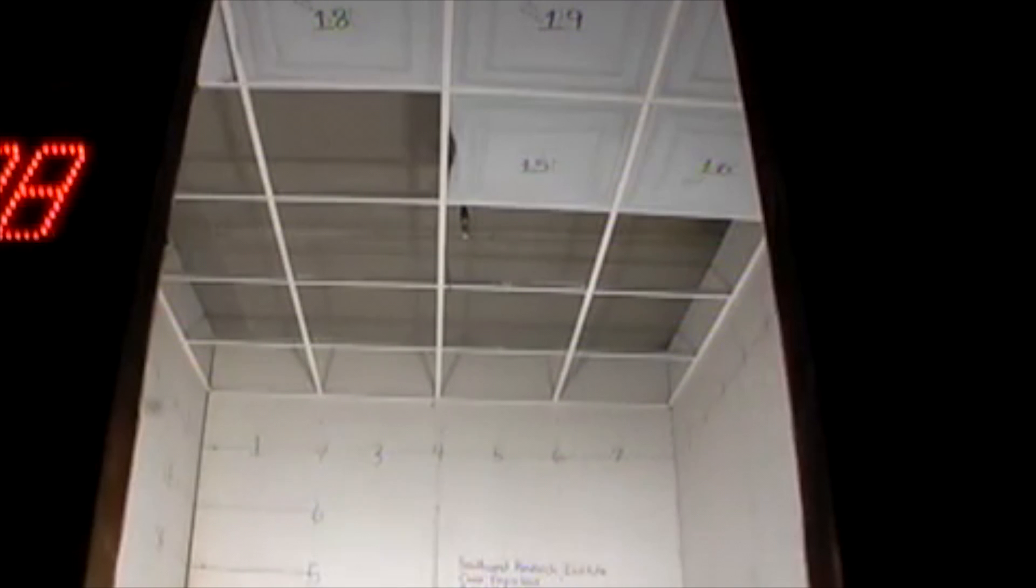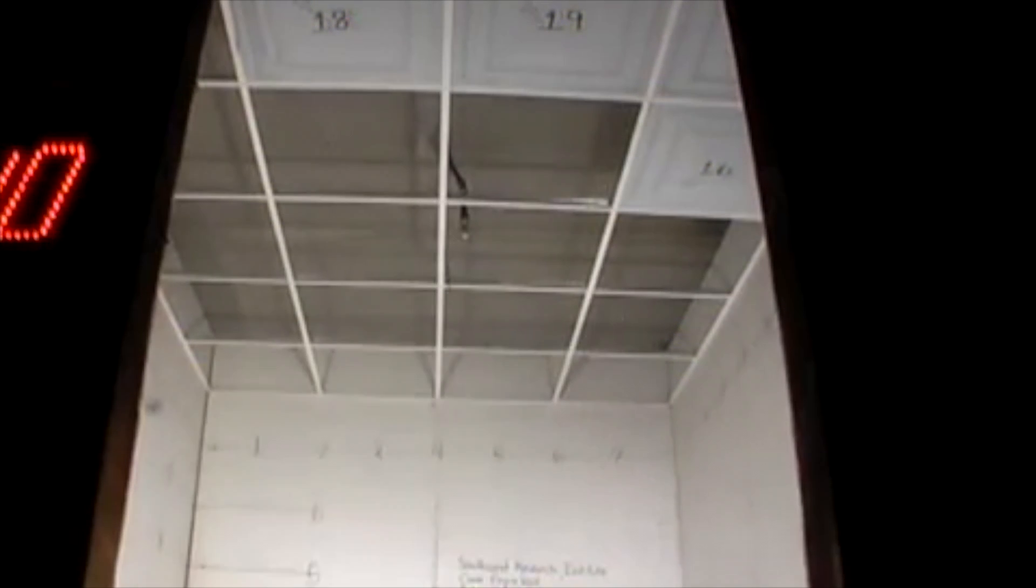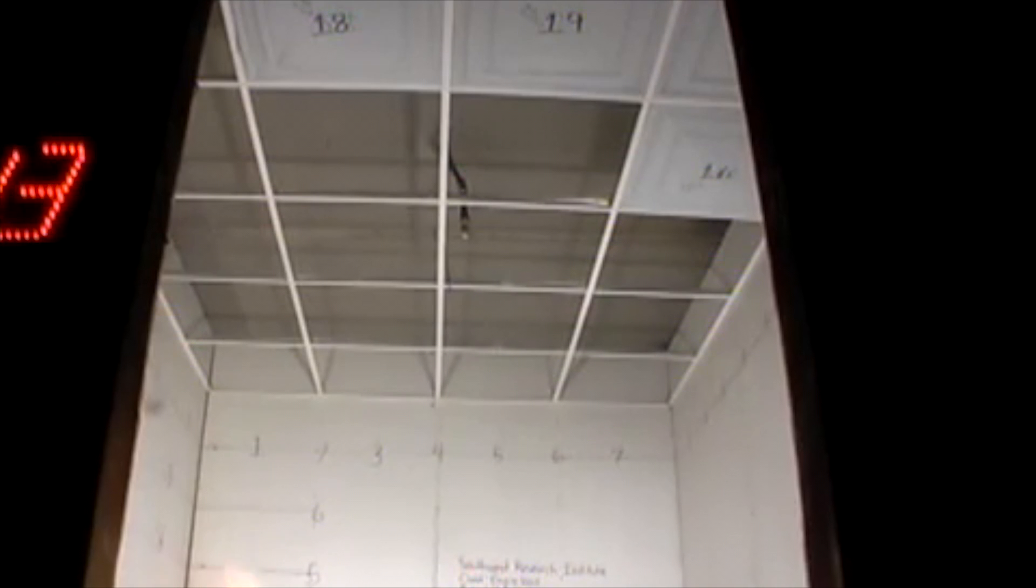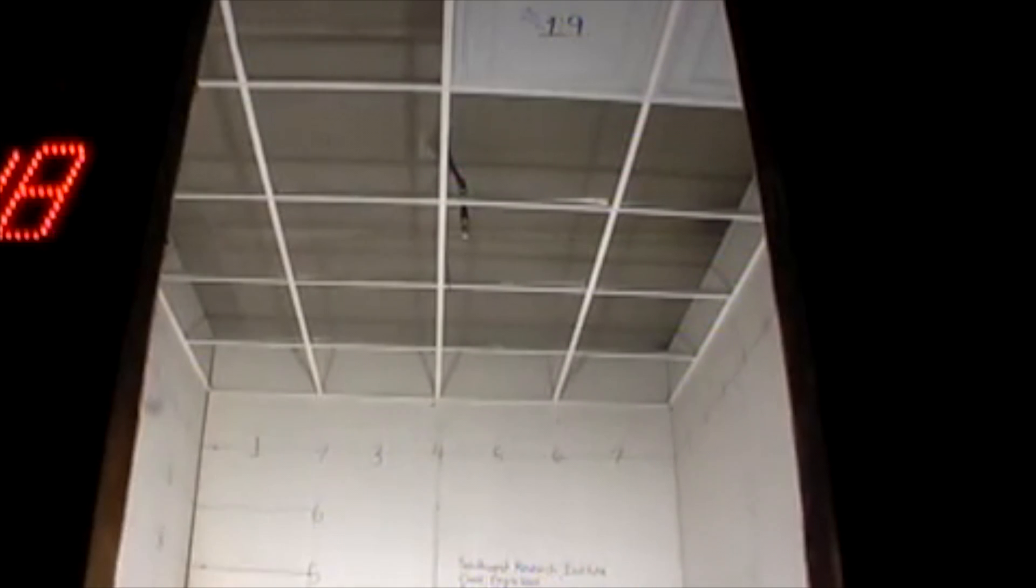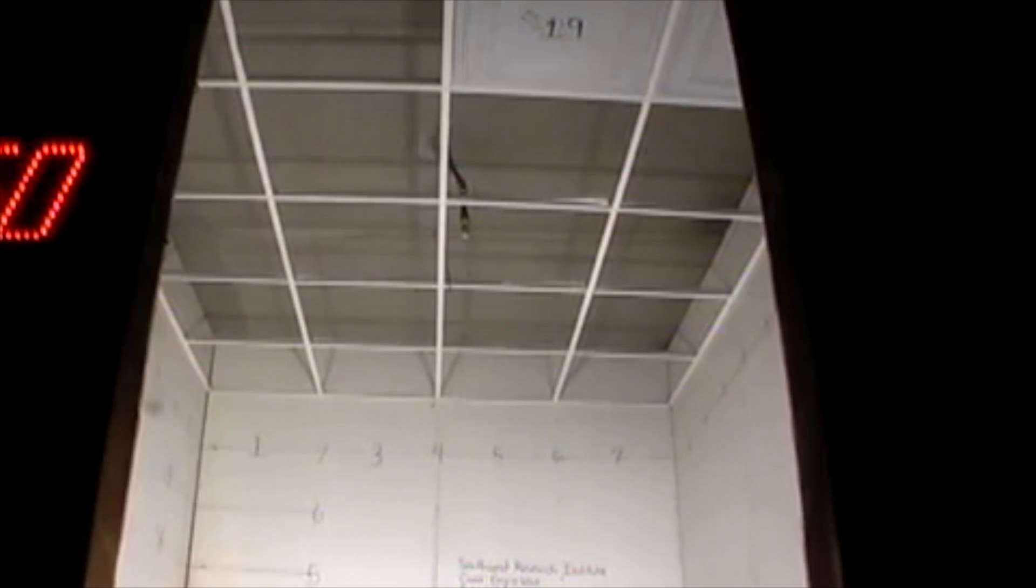Dropout ceiling panels work because, like fire suppression sprinklers, they are heat activated. Sprinklers can be located above them because the panels drop from the grid at below the sprinkler activation temperature. When heat from the fire activates the sprinklers, the panels are no longer there.